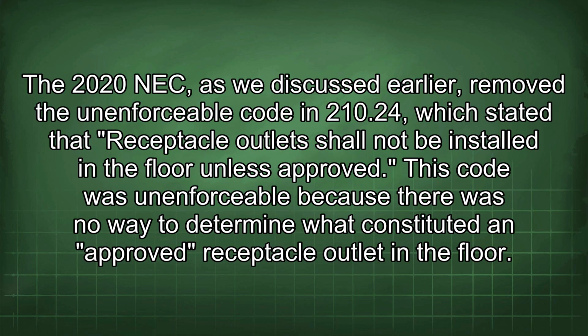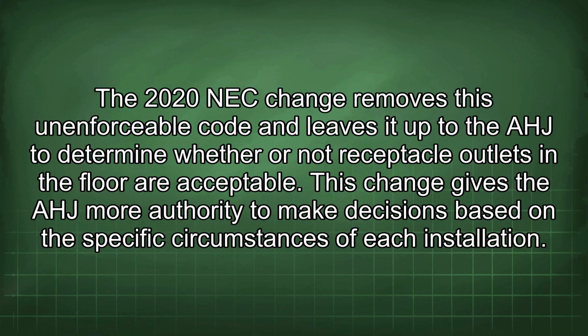The 2020 NEC, as we discussed earlier, removed the unenforceable code in 210.24, which stated that receptacle outlets shall not be installed in the floor unless approved. This code was unenforceable because there was no way to determine what constituted an approved receptacle outlet in the floor. The 2020 NEC change removes this unenforceable code and leaves it up to the AHJ to determine whether or not receptacle outlets in the floor are acceptable.